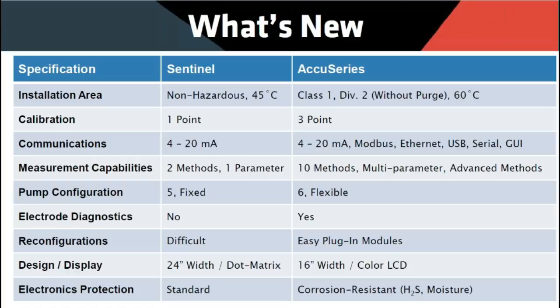The design of the display, we've made it a more narrow footprint. So space is often a consideration when choosing an analyzer. So now it's only 16 inches wide, and there's a beautiful color LCD with it. And then lastly, the electronics, so all of the boards have a special corrosion-resistant coating, which means that for H2S and moisture, it's not going to affect it.